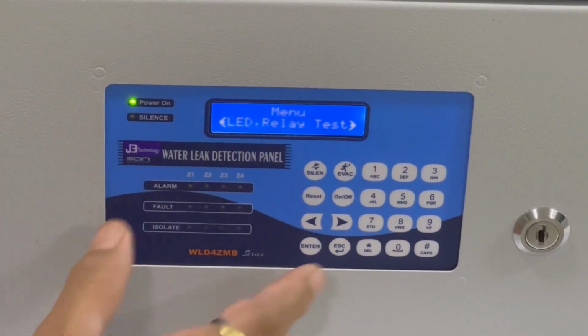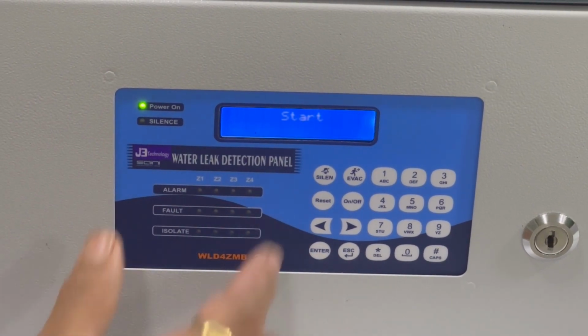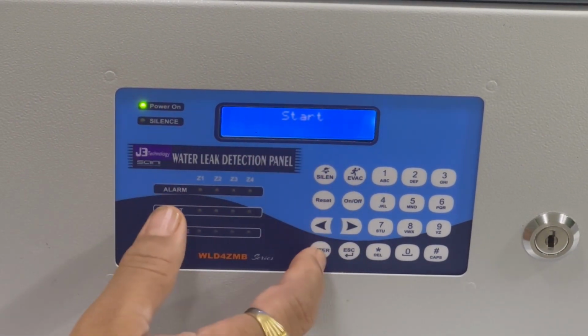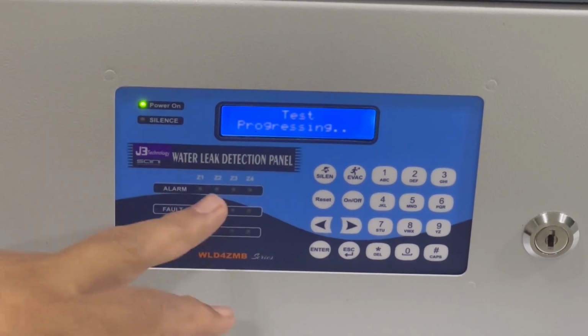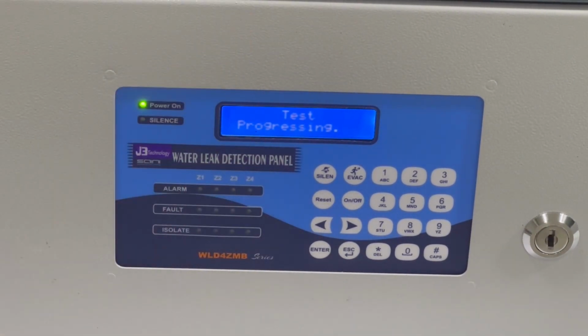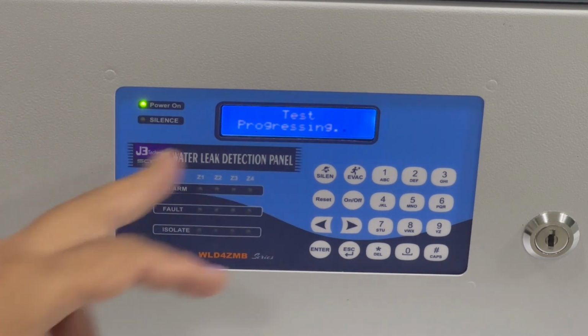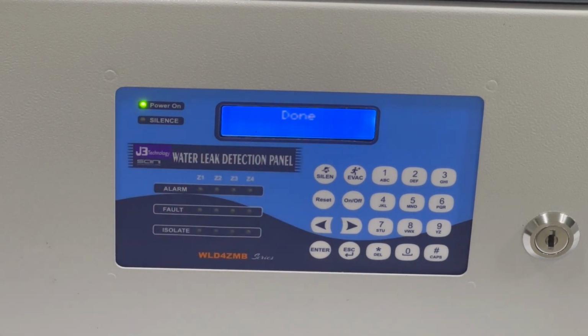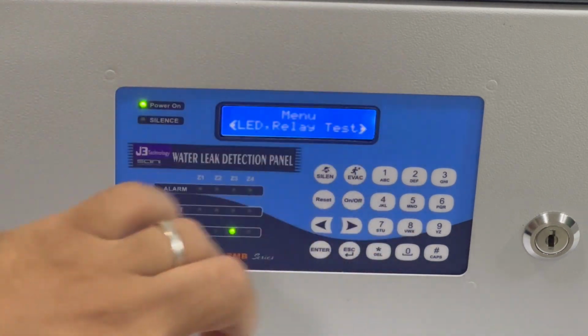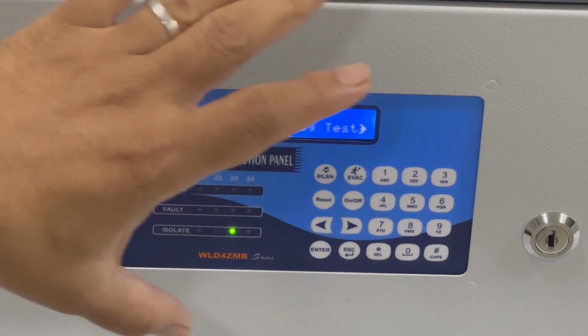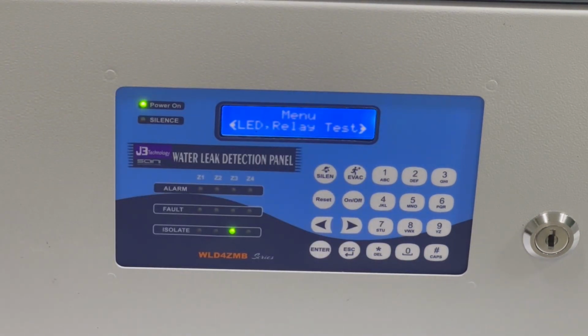You have to go to the relay side and press enter, and again it shows start. Press enter again. See, you can check all the LEDs glow. See, the hooter is also checked once to see that it is working. It shows testing in progress. So each and every function is self-tested by the panel itself, and this way you can check that all functions are working normally. This is the self-test feature available in our panel.